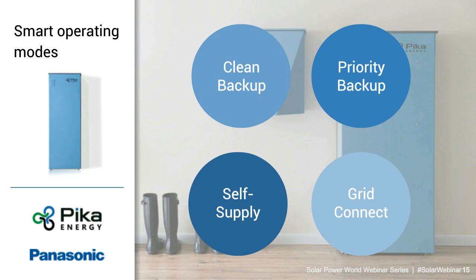The Energy Island system ships with 4 operating modes built in, and some of these can be tweaked as well for various applications. But the out-of-the-box applications that are available to all customers for the Pika Energy Island are 2 backup modes, clean backup and priority backup. Clean backup allows you to charge your battery directly from the PV and will not allow you to charge from the grid. Priority backup does allow grid charging. So that's a mode we recommend if it's available in the customer's jurisdiction to do grid charging for their battery.